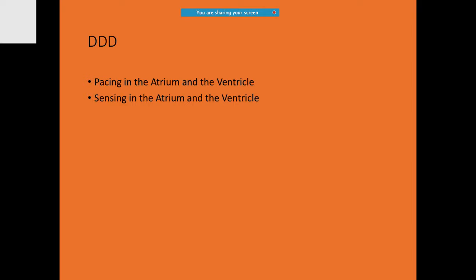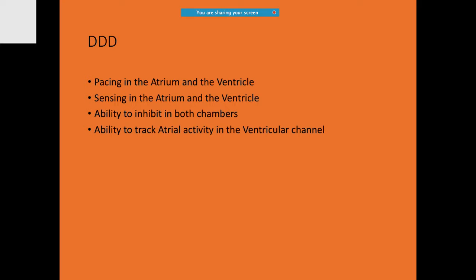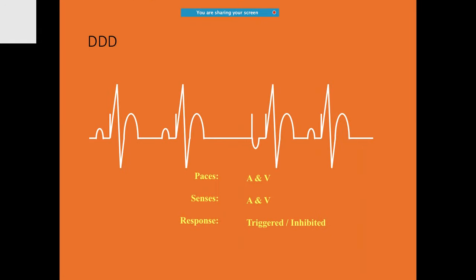DDD is the master of all — it paces in both chambers, senses in both, has both inhibitory and triggered responses, and has tracking ability. In the first two beats it sensed the atrial beat and gave a triggered response for the ventricle. In the third beat, when no atrial activity was sensed, it paced both atrium and ventricle. In the last beat, an intrinsic P wave was present so it paced only the ventricle.